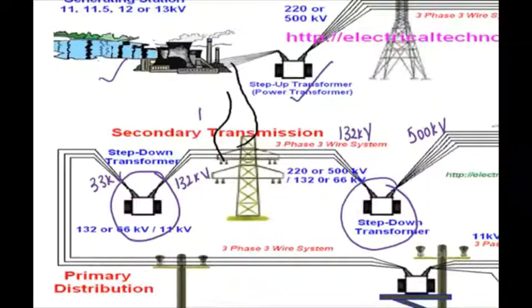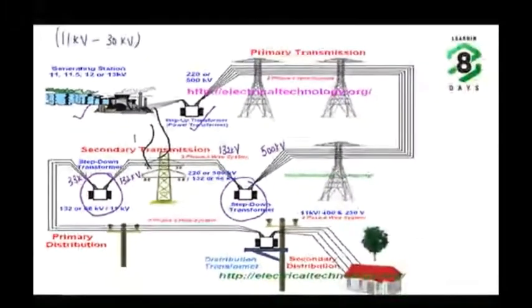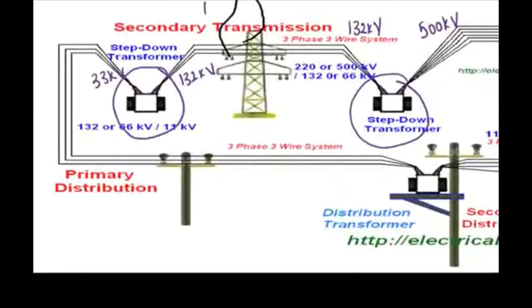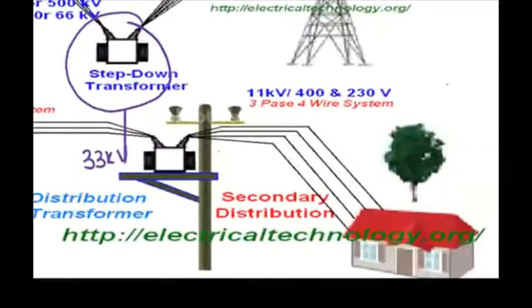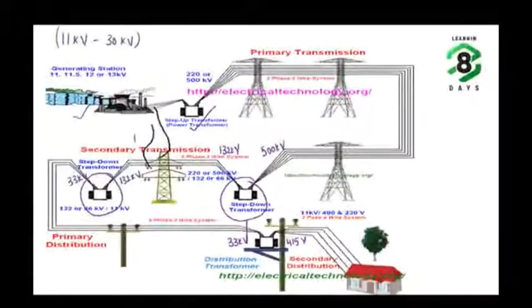So after this stepping down, the primary distribution starts. Primary distribution again is carried by a 3-phase 3-wire system. So again here it will be stepped down to the nominal voltage. Suppose the primary voltage is 33 kV, it will be stepped down from 33 kV to 415 volts. So again it would be distributed at 415 volts to the domestic customers. So vaguely you have a generation, you have a step up transformer, transmission, again step down transformer, again the secondary transmission, again you are stepping down the voltages and bringing down to the voltage levels which we have to distribute to the customers. Industrial customers can be directly fed at higher voltages, say they may be fed at 132 kV or 33 kV directly, depending upon the requirement.